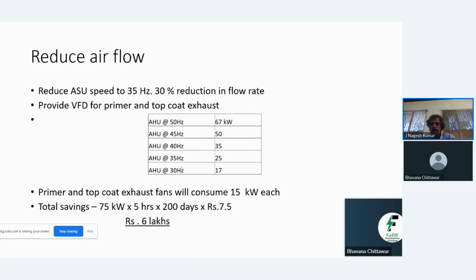At 30 hertz, we find that it is sufficient, because the production is not the same as it was envisaged to be. It was 16 to 18 units per hour. Now it is only 8 units per hour. So correspondingly, the fume generation is less, and the ventilation rate can be reduced by fine tuning the VFD to 30 hertz. And of course, as a precaution, we have set it at 35 hertz.